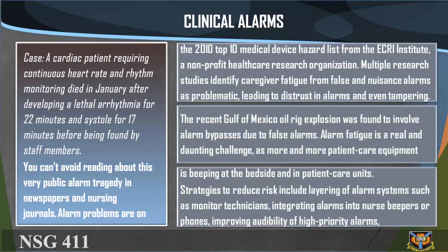The recent Gulf of Mexico oil rig explosion was found to involve alarm bypasses due to false alarms. Alarm fatigue is a real and daunting challenge, as more and more patient care equipment is beeping at the bedside and in patient care units. Strategies to reduce risk include layering of alarm systems such as monitor technicians, integrating alarms into nurse beepers or phones, improving audibility of high-priority alarms, and modifying equipment so alarms can't be turned off.